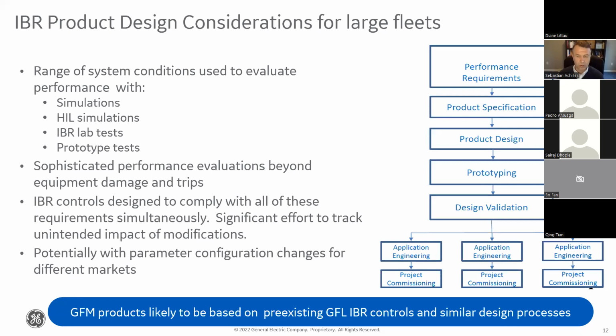In the past, we used to check if the equipment would trip or get damaged during the design validation. These days, we have to check that we meet all these performance requirements in terms of how the reactive current and active current behave, how the DC components get reduced, or whether the negative sequence behavior is acceptable. All of those things are part of this design validation done at the product level.